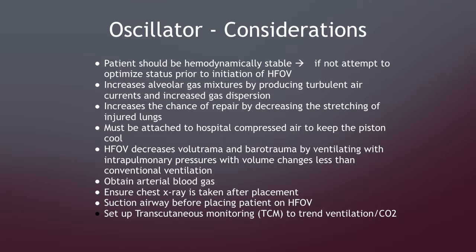Just some circuit things. You're going to have to make sure that it's attached to hospital compressed air to keep the piston cool. Some studies state that in ARDS patients the oscillator decreases volume trauma and barotrauma by ventilating with intrapulmonary pressures with volume changes less than the conventional ventilation.